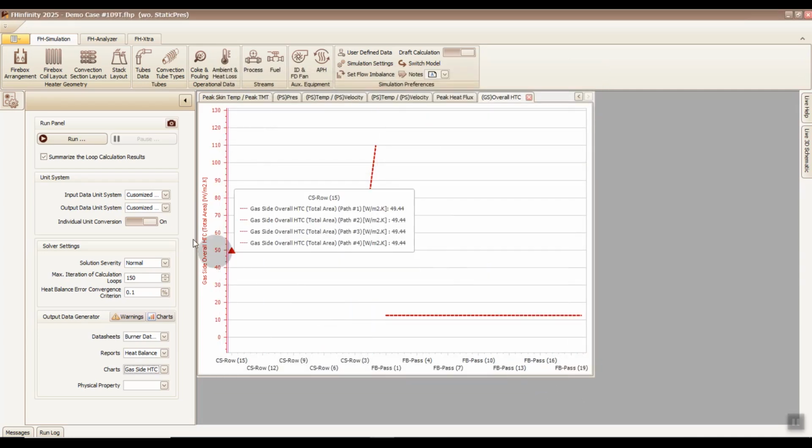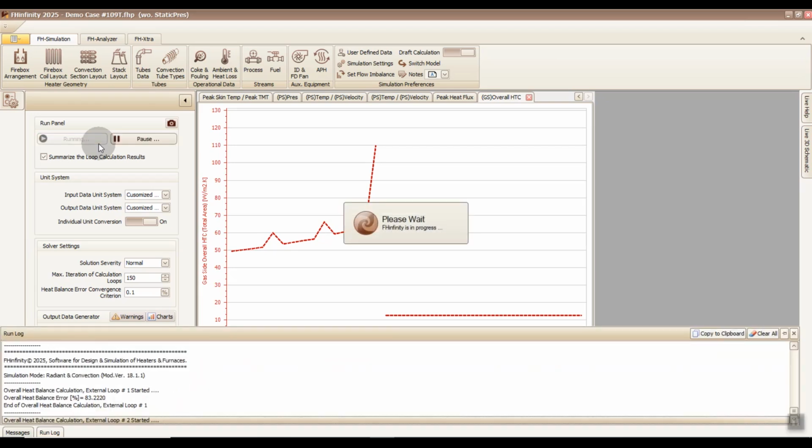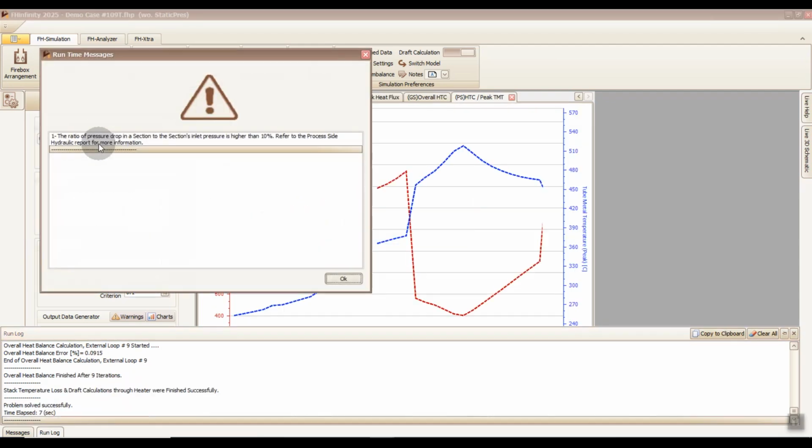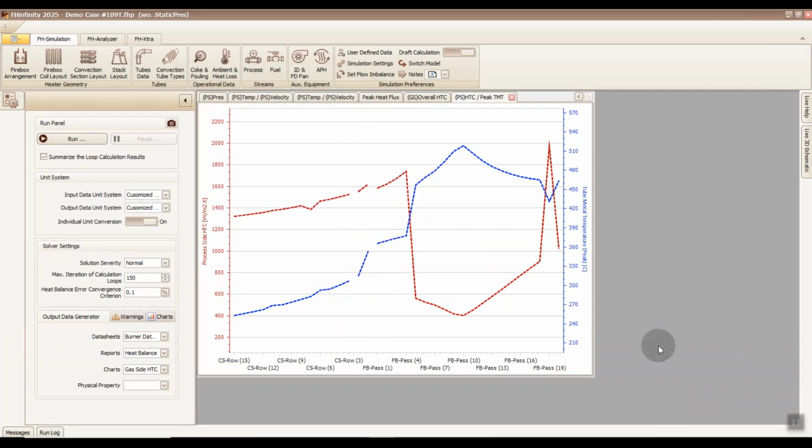The proprietary method calculates HTC by explicitly accounting for both the heat transfer region and the flow regime. A critical distinction: while this level of detail may not drastically change overall heater efficiency or outlet temperature, it has a direct and significant impact on tube wall temperature predictions.